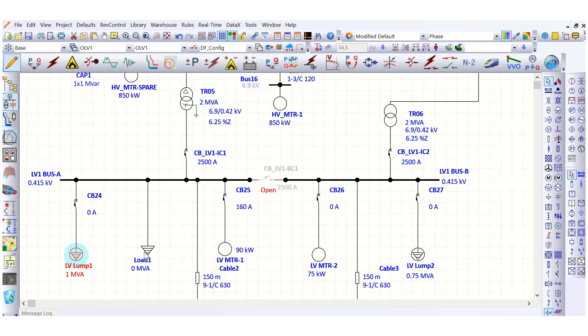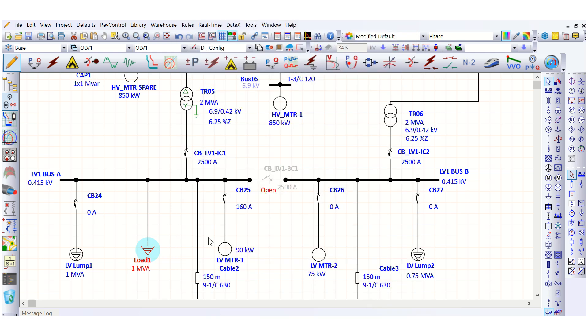Now let's go to the static load. Under the loading page, we will put the same value of 1 MVA, just like the lump load. The power factor here is 100% by default, because this is a 100% static load — that means 100% power factor. So as of now, we have 1 MVA lump load and 1 MVA static load modeled.